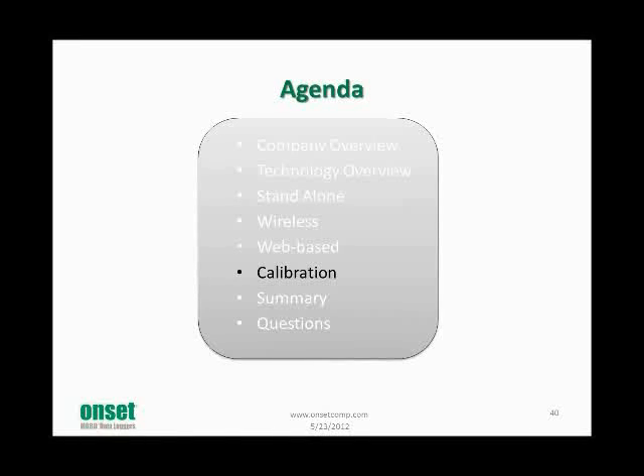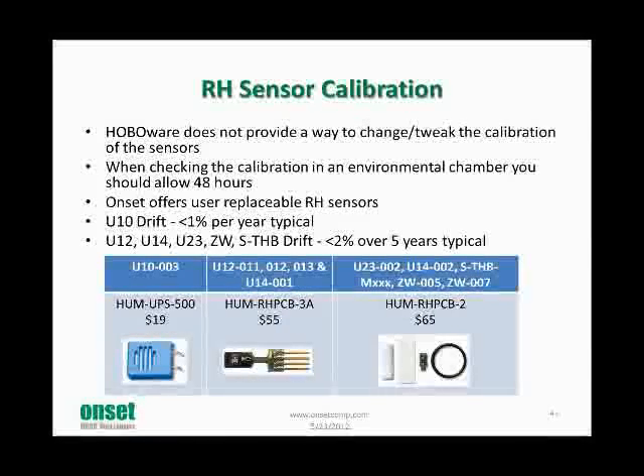So calibration - as I look here at the list of questions, there's a good half dozen - how do we deal with calibration, and I'm going to focus on humidity because that's really the critical one. Temperature, our thermistors, we use a thermistor, we do not use RTDs or thermocouples. For the limited range that we're recording in, the thermistors work very well and they're very stable. Usually if you see something goes out of whack, it begins recording at -600 or something like that, and at that point it's usually a component failure, and we recommend obviously calling us and talking to our technical folks, and they'll get you kind of taken care of.